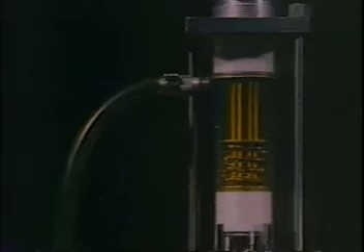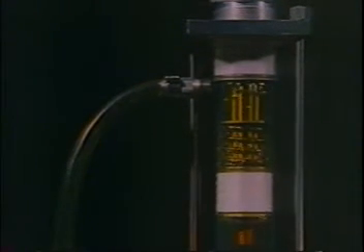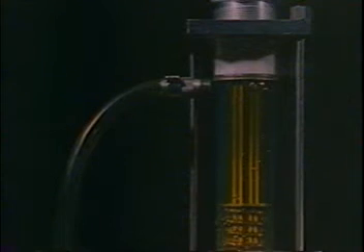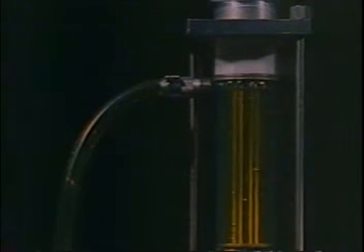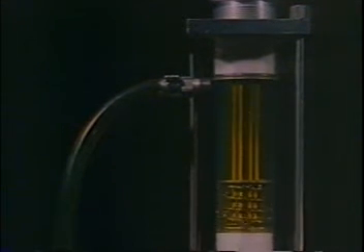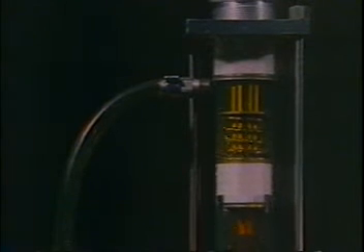A self-purging air bleed fitting on the bottom of the piston purges air from the lower chamber, and by placing the side connection to the upper chamber at the very top, the entrapped air is automatically purged from the pump with the outward flow of liquid.